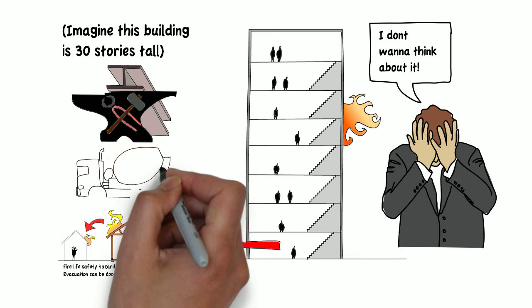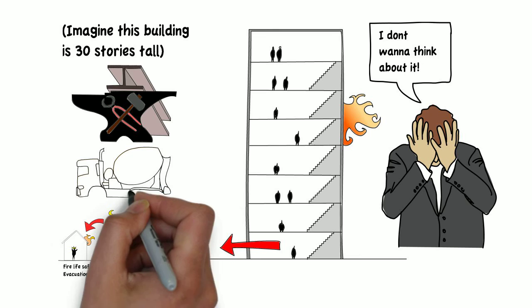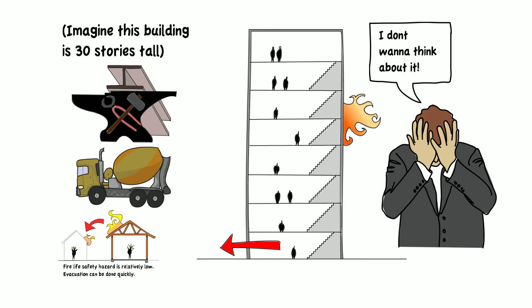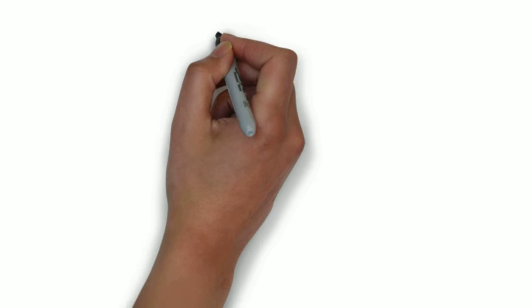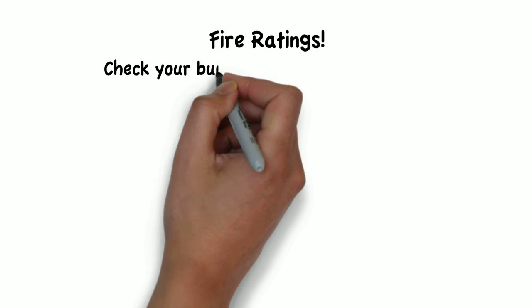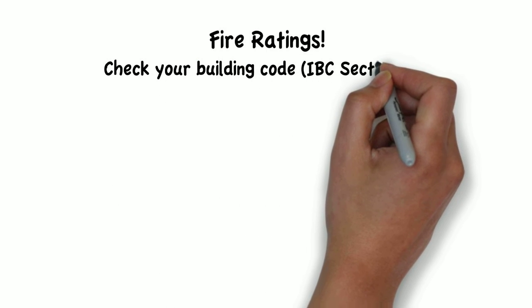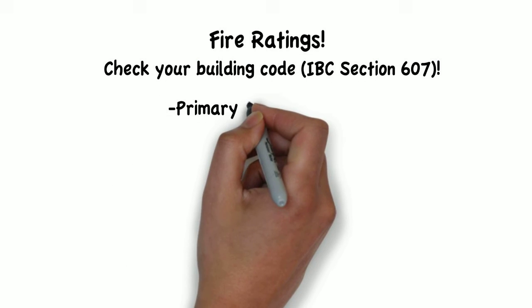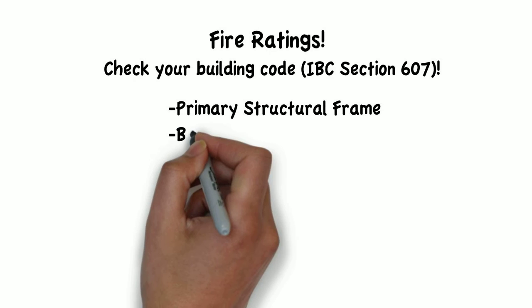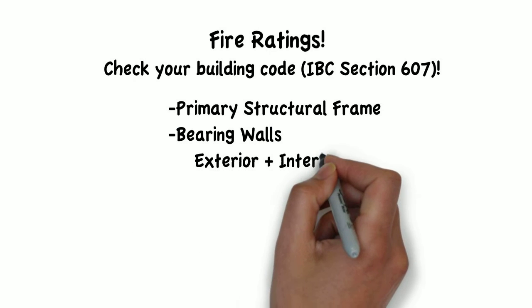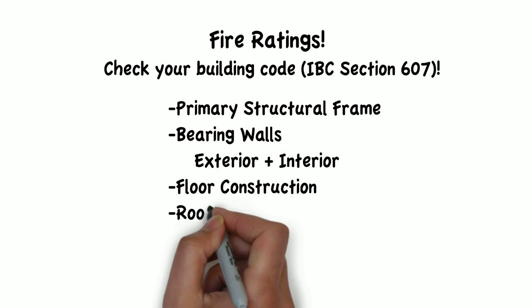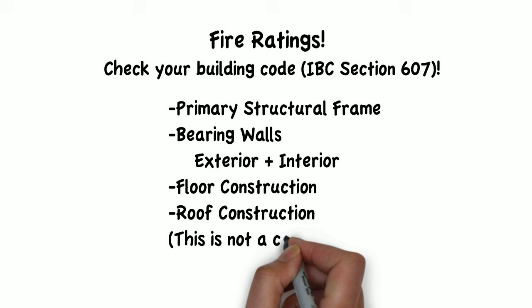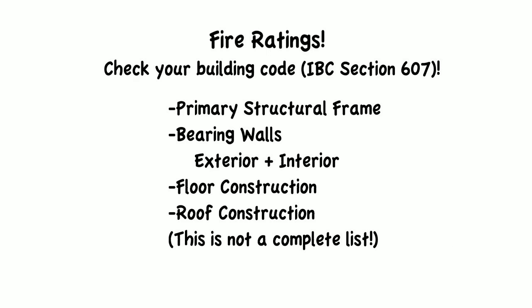But using concrete and steel alone doesn't always provide the protection you need. That is why there are also fire rating requirements to protect specific building elements. The building code specifies the types of systems that are most important for fire life safety - the structural frame, bearing walls, floor systems, and roof systems.